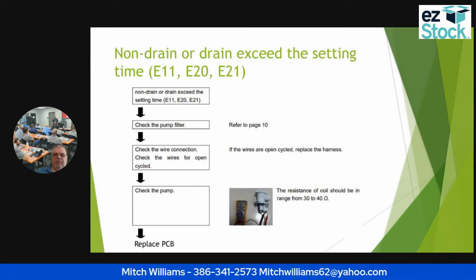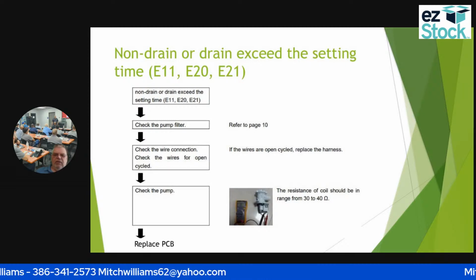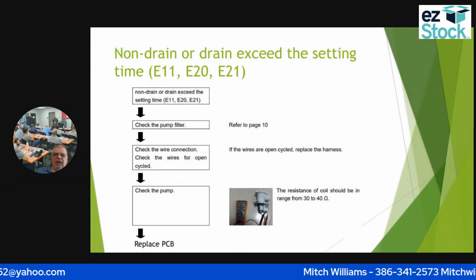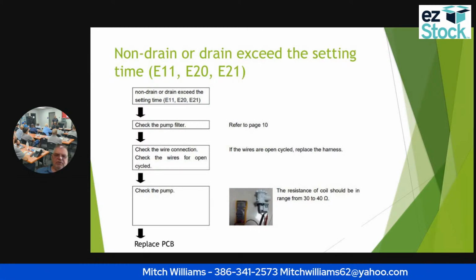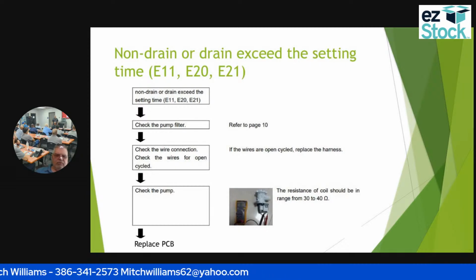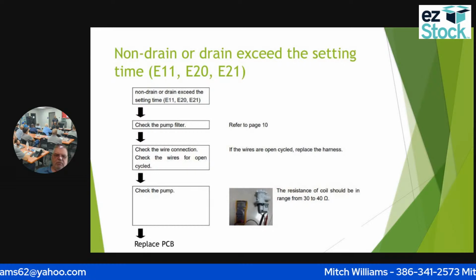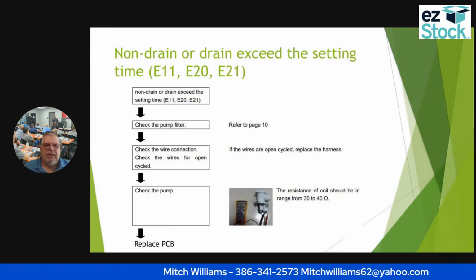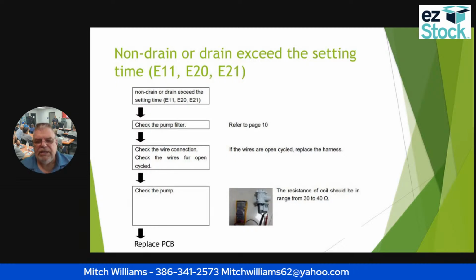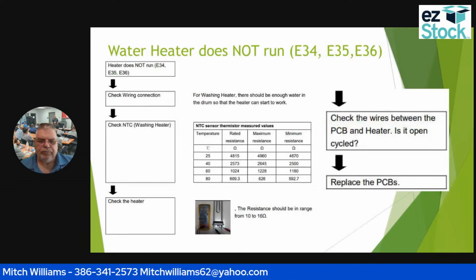And then lastly, I'm going to check the pump. The resistance coil for this pump should be about 30 to 40 ohms. So I'm going to check it. I'm going to flip it over to the ohms scale, and I'm going to check that ohms for the coil, and that should be somewhere between 30 and 40 ohms. If I get all of that and that works, that means that I've got a bad PCB, and I'm going to have to replace the PCB.